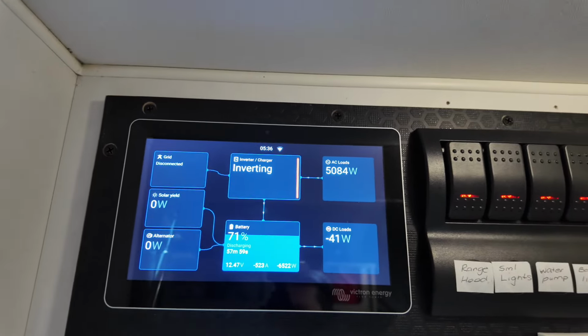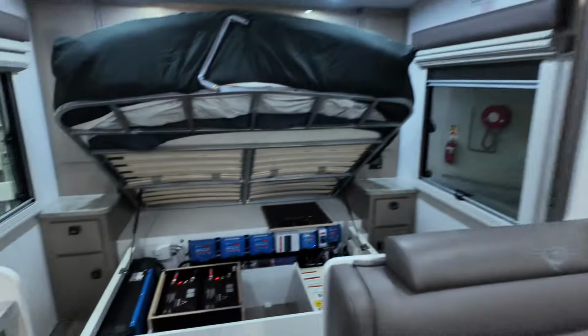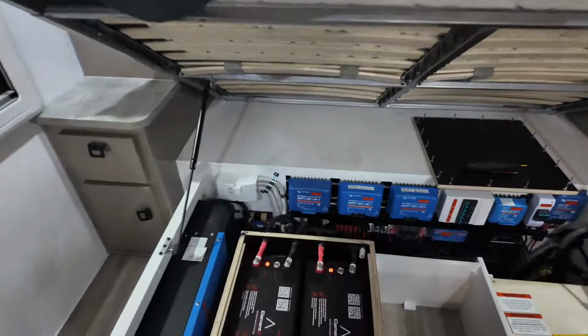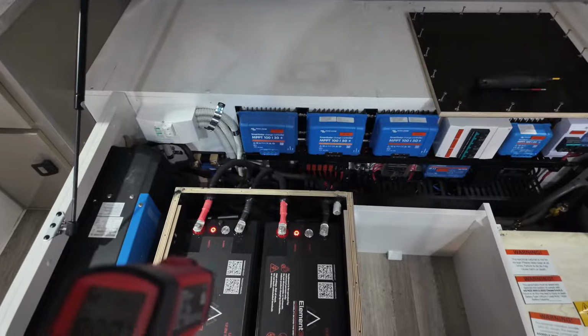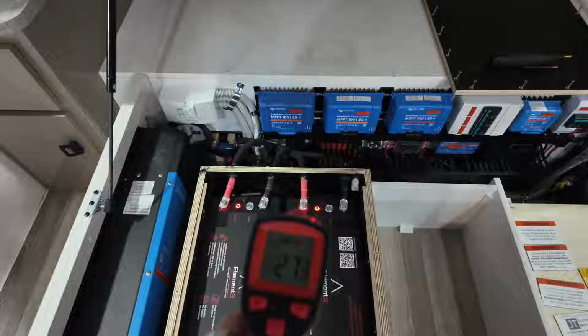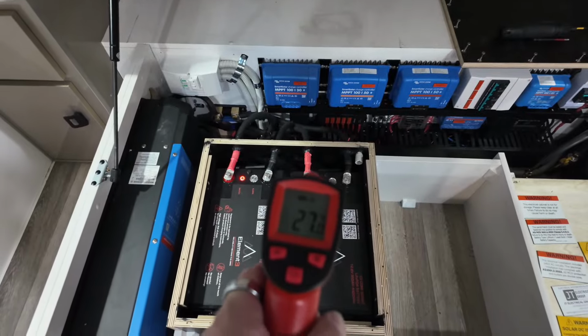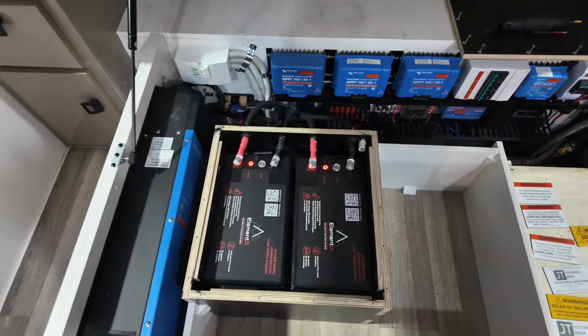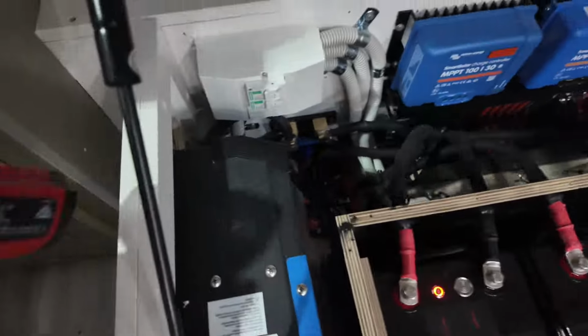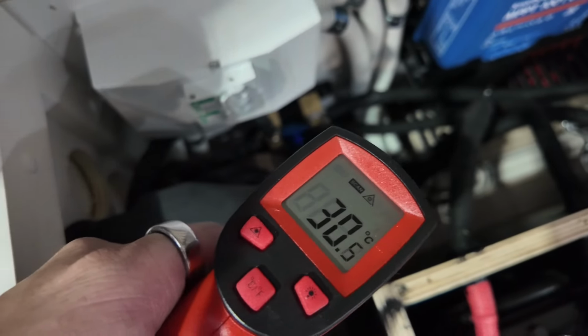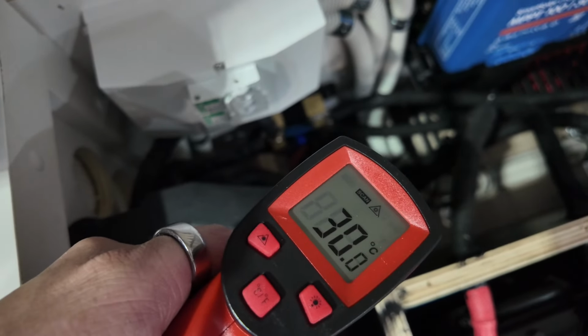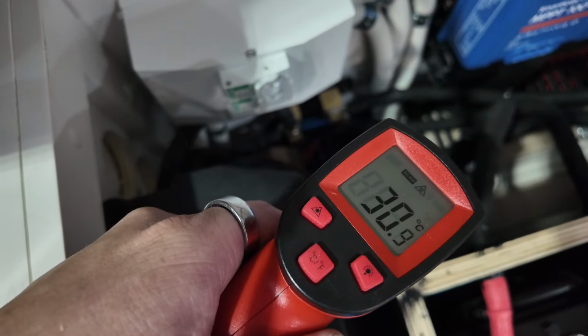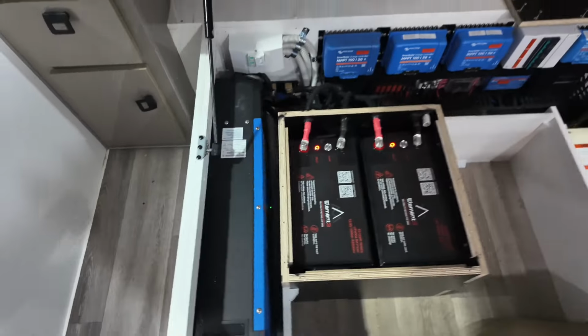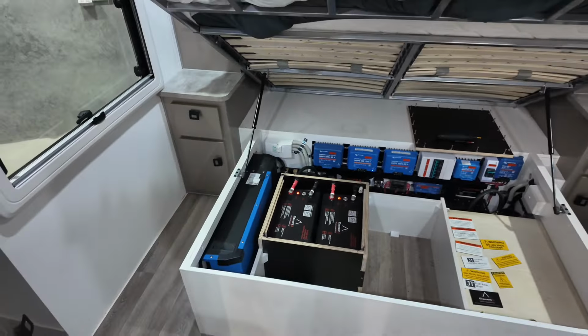Battery's handling it, inverter's handling it. Yes, the internal temperature of the inverter is going to get warm, but you can't do much about that, that's what the inbuilt fans are for. Terminal temperature, we're getting up to 27 degrees now, still absolutely well within our guidelines. And then down at the circuit breaker, it's 30 degrees. So we're doing perfectly fine here.